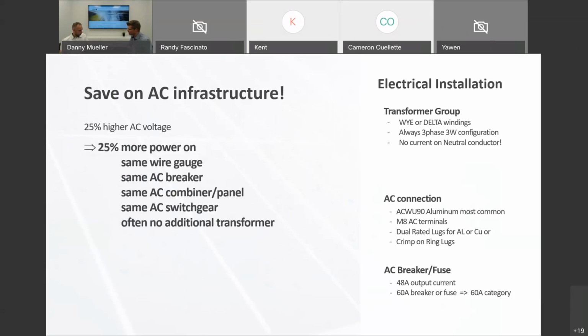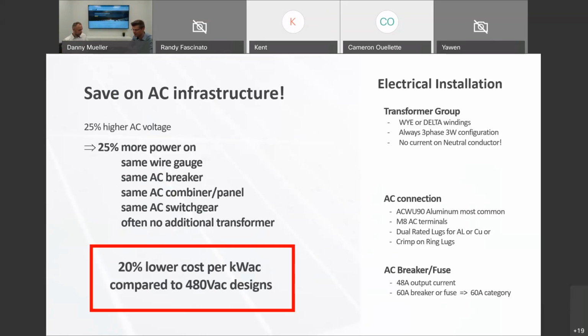The main difference, as we already discussed, is that the inverter is connected to a 600 volt AC system, and most other inverters on the market are typically designed, again, for North America and have a native voltage of 480 volts. The higher the voltage, the more output power you can get out of the system at the same output current, because with inverters, typically, you pay for current. And if you have a 600 volt design versus 480, you already have from the start about 25% higher voltage, which means with the same AC infrastructure, so the same wires, the same breakers or switch or fuses, the same electrical panel you buy, the same switchgear, and with no additional step up or step down transformer, you already optimize the cost and the equipment you deploy versus going with a more common US-based 480 volt concept.